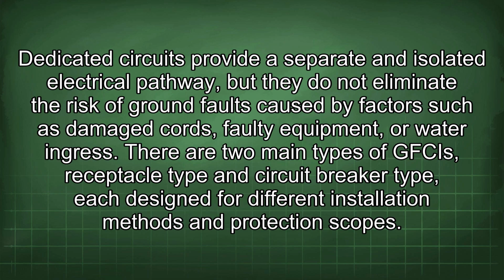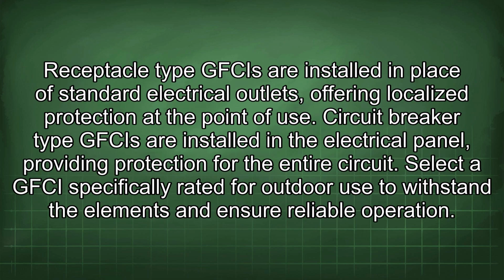There are two main types of GFCIs, receptacle type and circuit breaker type, each designed for different installation methods and protection scopes. Receptacle type GFCIs are installed in place of standard electrical outlets, offering localized protection at the point of use. Circuit breaker type GFCIs are installed in the electrical panel, providing protection for the entire circuit.